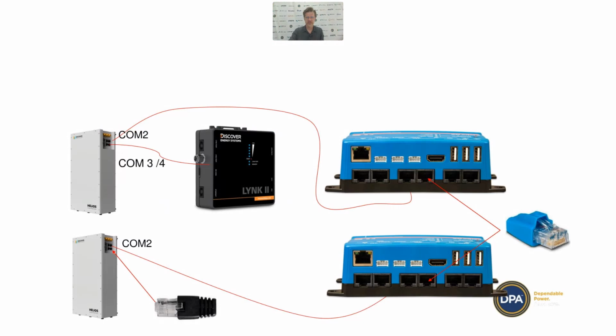Here's a little diagram. We're going from COM2 of the Helios into the CAN bus, with end terminator plugs. If you're using a LYNK II, that goes into COM3 or 4 on the Helios. If not, you'll just use the terminator into COM3 or 4. If you're linking multiple batteries, link them together with a normal RJ45 cable from COM3 to COM3, or COM3 to COM4, doesn't matter, and have a terminator in one of them. The terminator comes in a little bag with the black RJ45 cable that comes with the battery. It's easy to lose, but we now have plenty of spares on the shelf, so if you do lose it, let us know, because it's difficult to make one yourself on site.